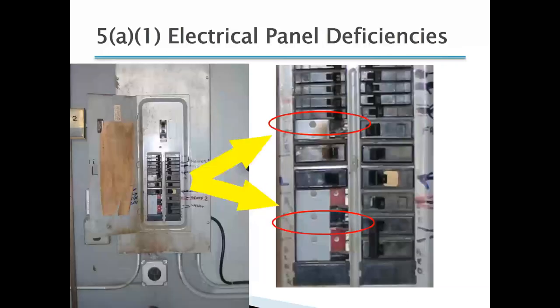Second 5A1 illustration, showing an electrical panel. On the left-hand side, opening up this panel, the directory is all washed out, so we have no idea what the circuit breakers are controlling. We want to know if we have an emergency and need to open the panel and shut off the specific circuit breaker that controls a piece of machinery. On the right side, we have circuit breakers missing — I've seen people put cardboard with a skull and crossbones saying danger, or duct tape over the opening, and that's not acceptable. The concern is an employee reaches in to flip a breaker off, their finger slips, and they make contact with the energized bus bar. All these openings have to be safeguarded — you should put a circuit breaker back in or an approved blank to safeguard those exposed energized parts.